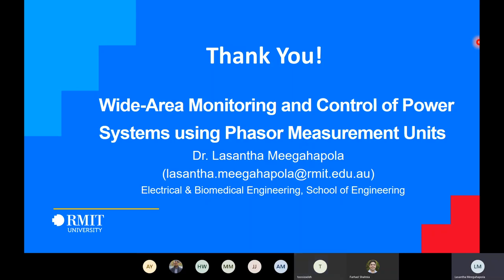Probably you are right, but in this particular research, we didn't consider any of the other types of generating sources, because our ultimate objective is to identify the discrepancies which could happen because of different types of algorithms. But of course, your point is exactly right, because when you have electronics-based sources, you definitely have to have more components built into your phase measurement algorithm to remove the unwanted components, especially the high frequency harmonics coming into the system.